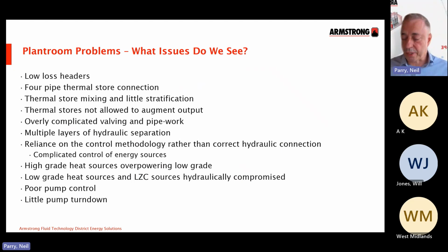We see low loss headers. What low loss headers do is they allow circulation back to the energy sources, and so they increase the return temperature going back to the energy sources, so they should be avoided. If you need to have headers, then a flow header and a return header, not connected as 2 separate headers. We see thermal stores connected in a 4-pipe arrangement, and in that arrangement it is just operating as a low loss header again. Thermal stores integrated in such a way where they're not allowed to augment the output of your energy sources, something we'll touch on later, and then overcomplicated valving and hydraulic arrangements around those thermal stores.